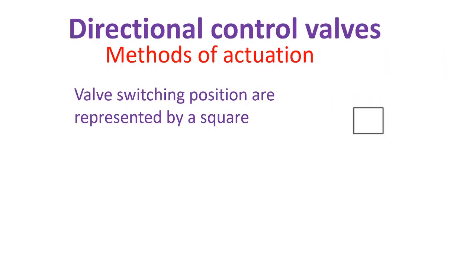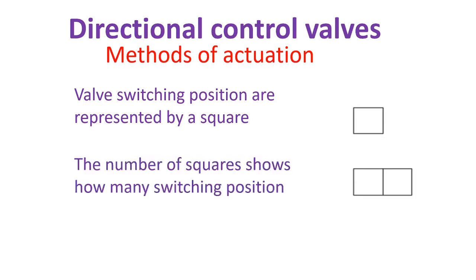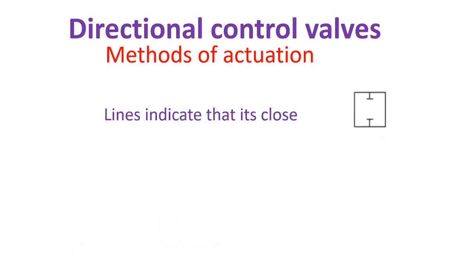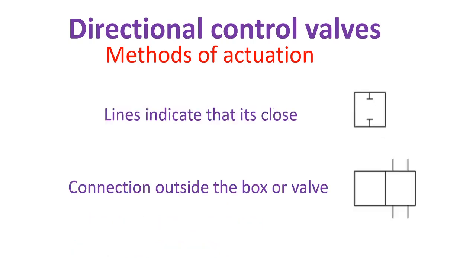Now let's get started on how to read directional control valves. Valve switching positions are represented by a square. The number of squares shows how many switching positions. Lines indicate flow path, arrows indicate direction, lines indicate that it is closed, and connections appear outside the box or valve.